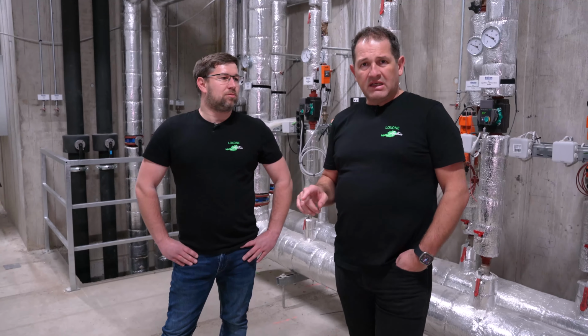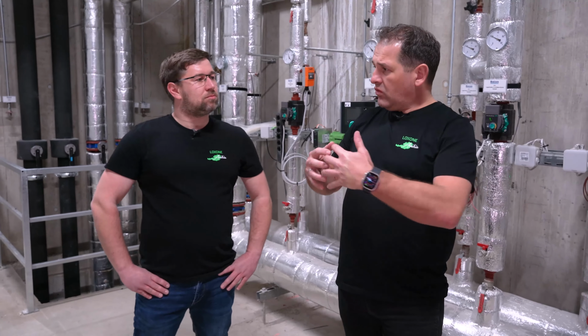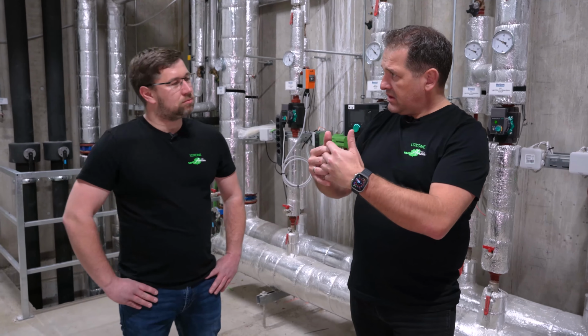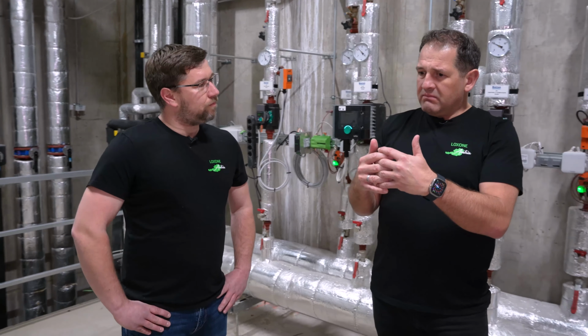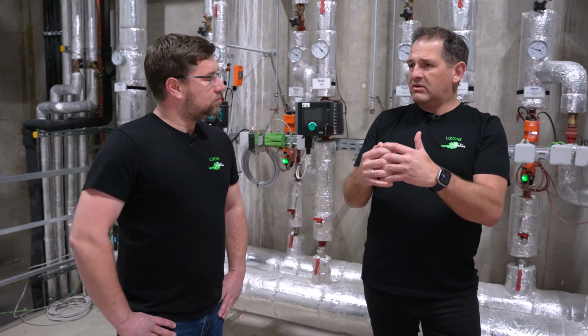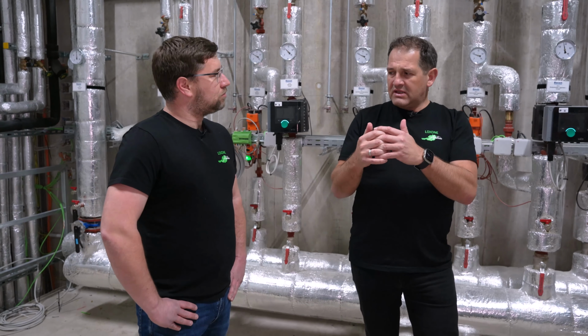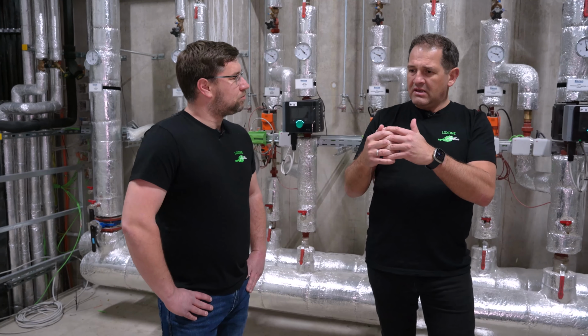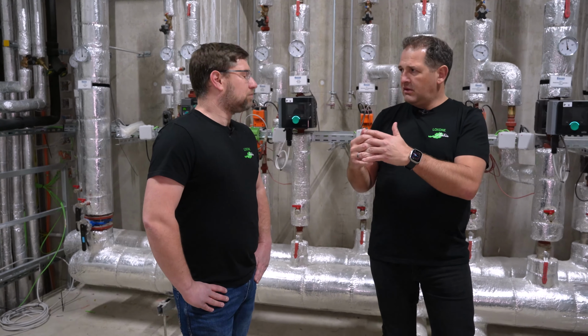The ventilation system operates in a self-sufficient manner, relying on information provided by the mini server located in the office. The primary objective for managing the 6,000 cubic meters of air is to achieve high air quality whilst minimizing the amount of ventilation required.